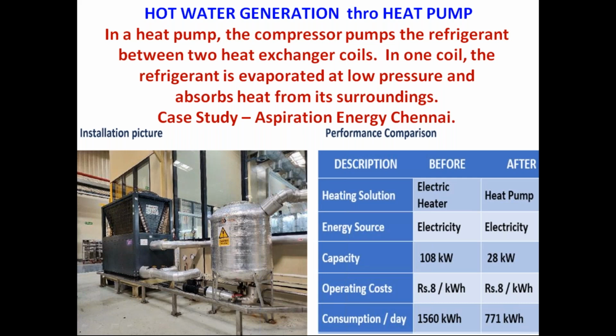When hot water is needed at 50 to 60 degrees or 70 degrees, a heat pump is an excellent retrofit choice. And solar water heating is the best because there is no consumption. In addition to that, it will be a preheating, and this will also be a parallel heat pump application, where the energy efficiency of a heat pump is almost 50% or say 100% more compared to the electrical heater. Next, please.